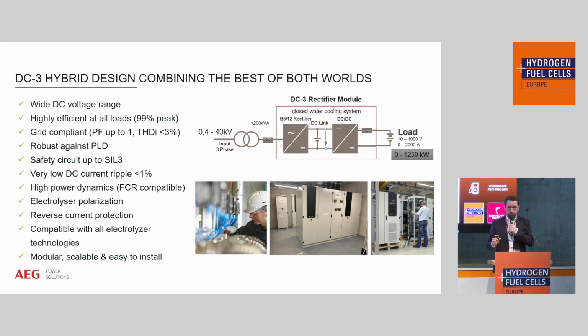And on the other hand, to operate the AC-DC thyristor-based rectifier at its optimal point of operation, meaning full duty cycle, which is very favorable for the low THDI we can achieve. As it's a buck converter design, we're able to operate at high voltages and low currents, which is very favorable for high efficiency. We've measured a peak efficiency of 99%.